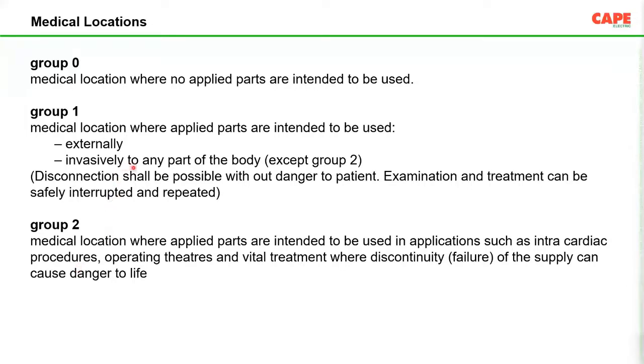Now, group 1 means a location where medical equipment is used externally, the applied parts are used externally. Group 2 means the applied parts are used internally, meaning sometimes the skin is bypassed and the equipment goes into the body. As I said, once the skin is bypassed, the resistance of the body is quite low, so you have to be very careful.